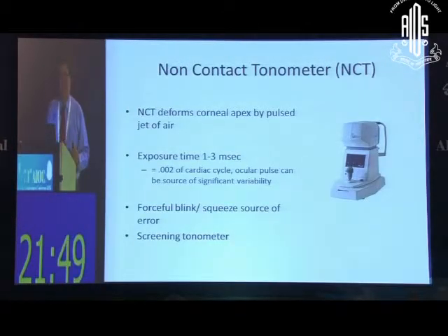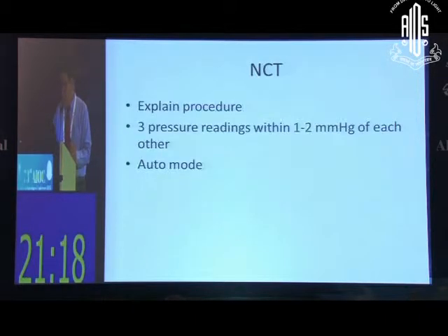Non-contact tonometer is again to be discouraged, but it's unfortunate that still a number of colleagues in India depend only on this. So why is it to be discouraged? It's a screening tonometer, and the reason for discouraging is that the jet of air that comes from the NCT makes some patients give a tight squeeze, and that gives a high pressure which is erroneous. And also there is a larger exposure time, and that may be affected by the ocular pulse. The pressure may be affected.